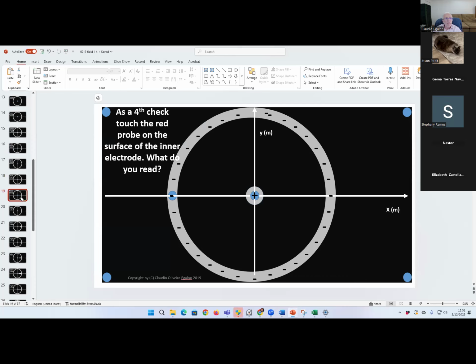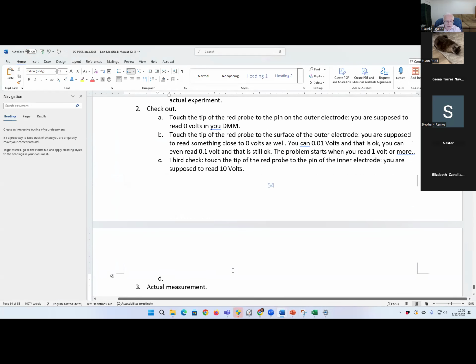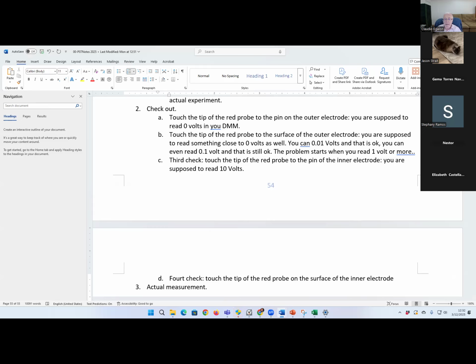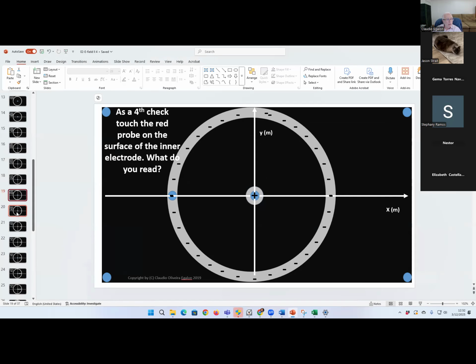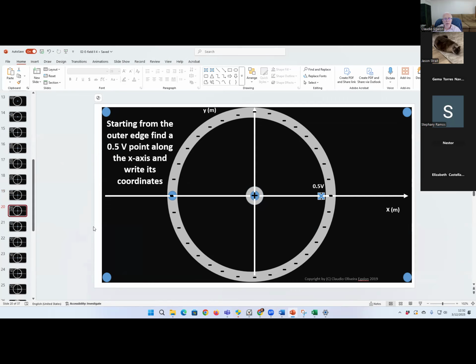is touch the red probe on the surface of the inner electrode, not the pin, but the surface. This surface right in here. You should also read 10 volts. Okay? Fourth check. Touch the tip of the red probe to the surface of the inner electrode, not the pin, the electrode. You are supposed to read 10 volts again. So those are the 4 checks that we do. Okay, and now we are ready to start the experiment.